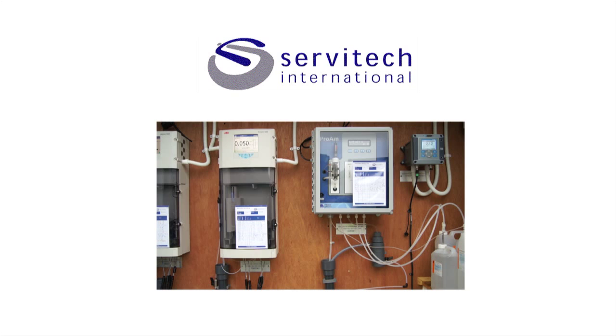ProAM Ammonia Monitor. You currently measure your ammonia levels by performing spot checks using a portable colorimeter such as a Palintest. That works by mixing your sample with a reagent and a colour is developed. The more intense the colour, the higher the level of ammonia in your effluent. The ProAM performs this analysis for you, but utilises a slightly different technique called ion selective electrode.